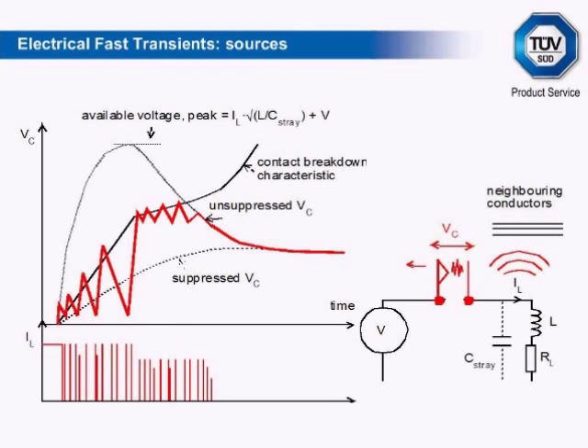The burst repetition rate varies from 10 kHz to 1 MHz. The supply wiring appears as a transmission line, so the line characteristic impedance determines the transient source impedance, and the transients themselves are easily attenuated by distance. As a result, these fast switching transients are only a threat to local susceptible equipment, but digital equipment in particular may easily be upset by them.